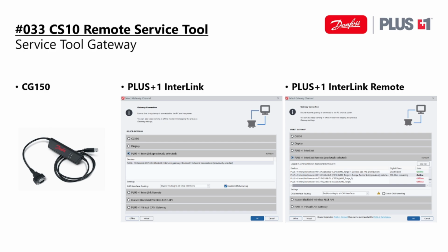Any CS10 is shipped with standard settings for Wi-Fi and Bluetooth. Wi-Fi works by default as an access point with the service set identifier, short SSID, followed by the EID. Wi-Fi is set to access point by default so it can be reached from the start. Bluetooth is enabled by default as well, and discoverable the first 90 seconds after startup. After you successfully select your preferred gateway to connect your PC to the CS10, you can start to configure the CS10 with the available CS10 diagnostic file.